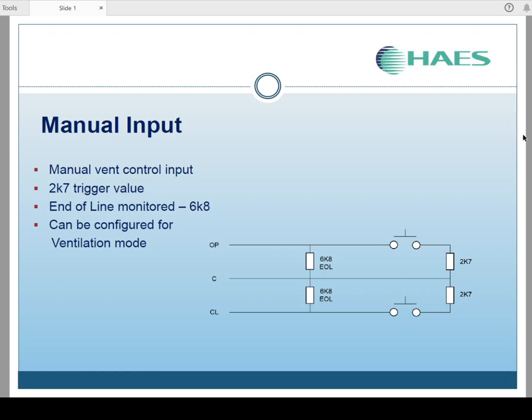The manual input is very similar. It consists of exactly the same monitoring with 6K8 end of lines between the common and open, common and close, and again 2K7 between common and open or common and close will activate the inputs. This can also be configured for ventilation mode, so you can fit a thermostat to these inputs to control the opening and closing of the windows via a thermostat control.